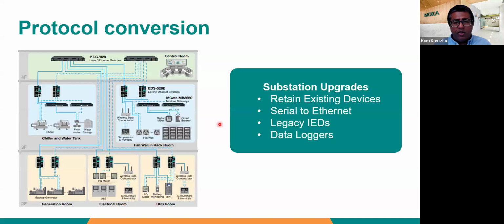Protocol conversion is another topic. As you modernize substations, obviously the substation has been built over a long period of time. There are a lot of legacy devices, and some of them may have been talking in different protocols, like Modbus or DNP3. How do we make sure those devices can also become part of the system? So you need to be able to convert some of these protocols, for example from DNP3 to 61850.